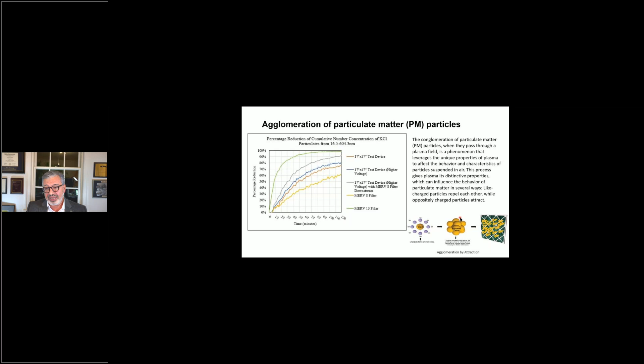So all three technologies, whether you're using UV lights or ionization or non-thermal plasma, will help you to control biofilm formation on cooling coils. Not only is it important for consideration of energy conservation, but it's also achieving dew point conditions, because you lose your dew point condition when you have these kind of biofilms that are forming. But more importantly, they generate mycotoxins, which again further complicates the indoor air quality equation by emitting these mycotoxins in this space. But as I said earlier, whether you're using ionization or UV lights or non-thermal plasma, all three technologies will afford you the potential of controlling biofilms. And biofilms is truly something that we should be taking into consideration in every single HVAC design.